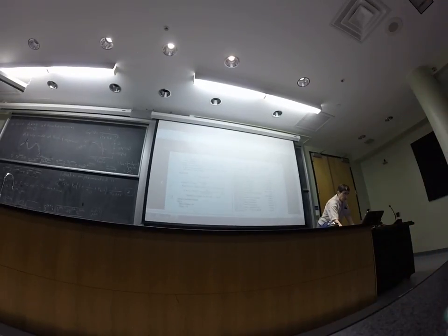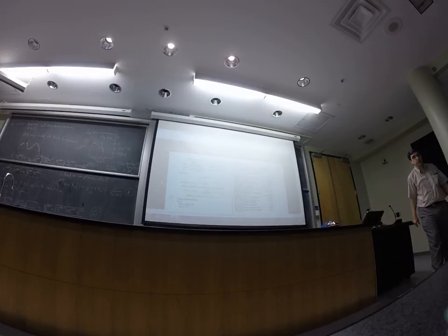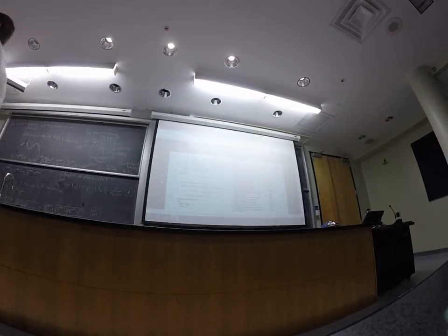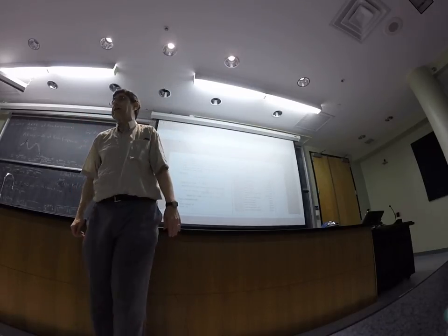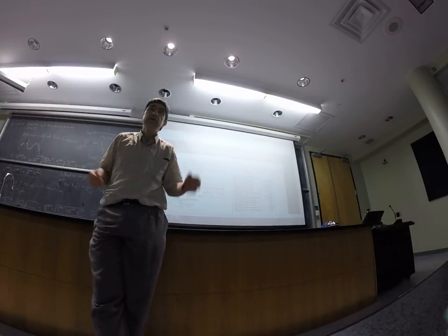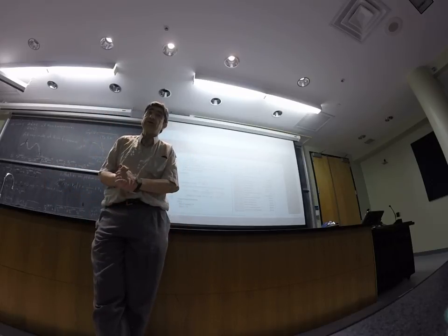If you look at the tuning, you see there is a range of parameters you can have. For example, the integral time constant goes from 0.01 to 1,000. If I could take tau I all the way to infinity, then I would have pure P control, no integral action. And probably at 1,000 it is going to be pretty close to no integral action, so you can probably use PI with tuning for tau I, the maximum being 1,000.